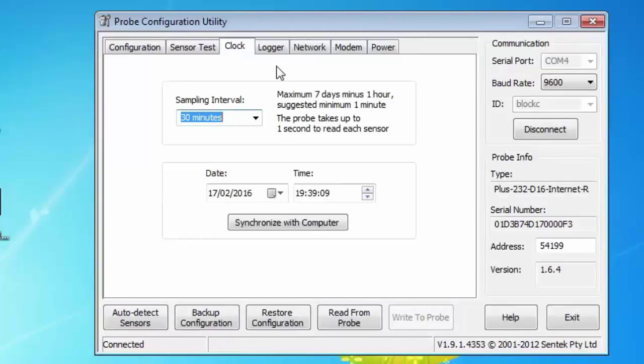Assuming we've finished everything, the last thing that's wise to do is to back up the configuration. Clicking on back up the configuration will back every setting up on this probe. So should the probe crash for whatever reason, if you've backed this up to a known location, you can at this point restore it back onto the probe, saving all of its settings.